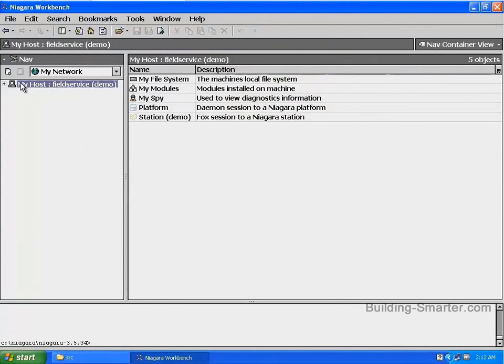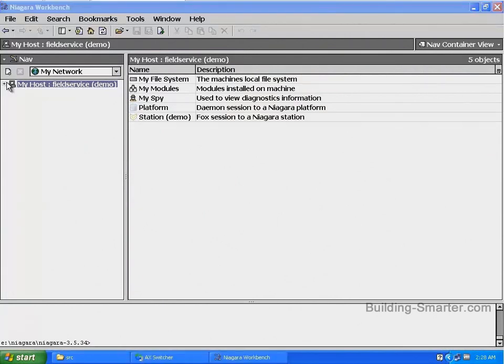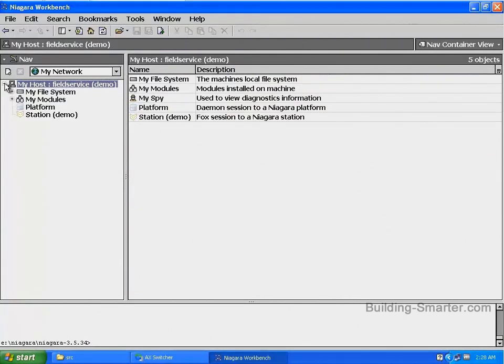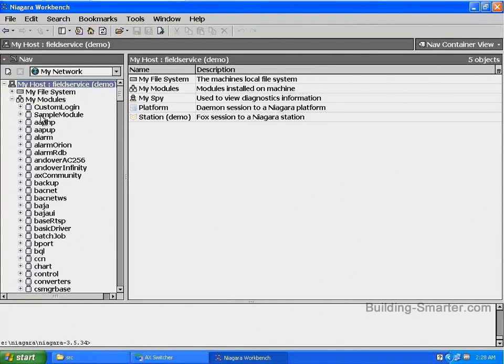After the build process is complete, you should see a success message appear at the bottom of the output. If you do not see success, check the path to your module and try again. To get your new module to show up in the list of available modules in the Niagara AX Workbench, you must restart your workbench to cause the registry to rebuild. Once workbench is restarted, in the nav pane, expand myhost, then mymodules — you should see the new module we just created at the top of the list. There it is: sample module. In this step, we did an initial build of our module. The purpose of doing this is to make it easier to find the path to our resources when we build our module.palette file in the next step.